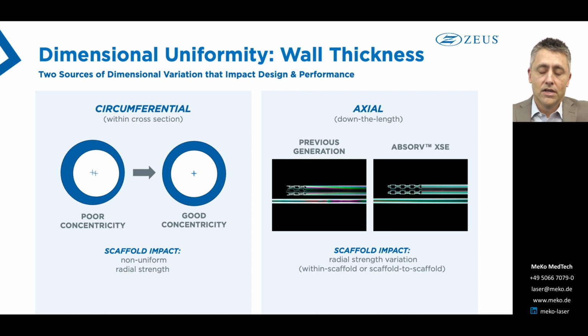So if you think about the inner and outer diameter of a tube, think about them as being two circles. It's really that center point of those two circles being misaligned. And what happens there is you end up with a thin wall on one side of the tube. And this can cause a BRS to have a non-uniform radial strength in that circumferential direction. Now, down the length variation can occur when the average wall thickness varies as you move down the length, and that can cause either within scaffold or scaffold to scaffold radial strength variation.